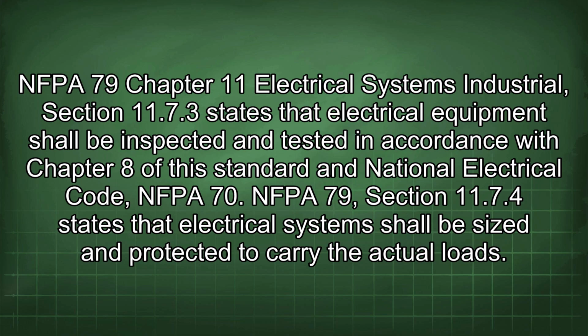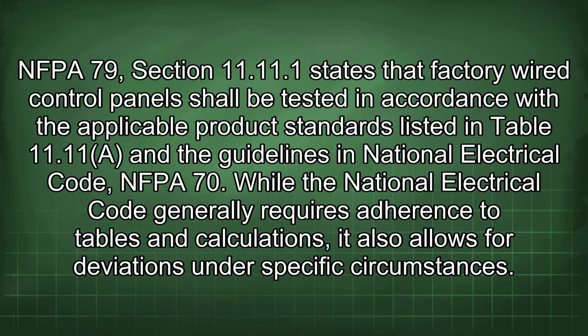NFPA 79 Chapter 11, Electrical Systems Industrial, Section 11.7.3 states that electrical equipment shall be inspected and tested in accordance with Chapter 8 of the Standard and National Electrical Code, NFPA 70. NFPA 79 Section 11.7.4 states that electrical systems shall be sized and protected to carry the actual loads. NFPA 79, Section 11.11.1 states that factory wired control panels shall be tested in accordance with applicable product standards listed in Table 11.11 and the guidelines in National Electrical Code, NFPA 70.